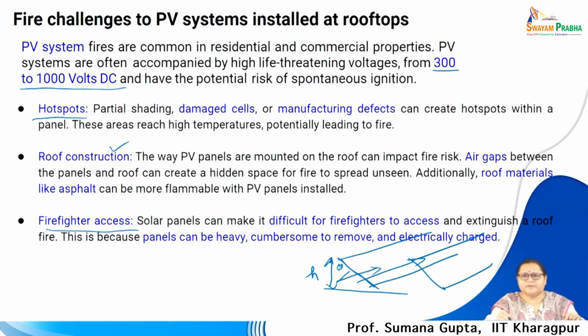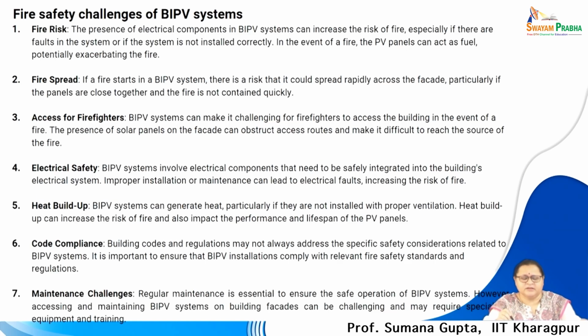These are heavy, cumbersome to remove and electrically charged. So, safety issues even for the firefighters is becoming a challenge for this. So, these areas are to be addressed properly. Fire risk, fire spread, access for firefighter, electrical safety, heat build-up, code compliance, maintenance challenges. These are areas which are to be addressed in the coming codes and standards, and already the codes are in place.